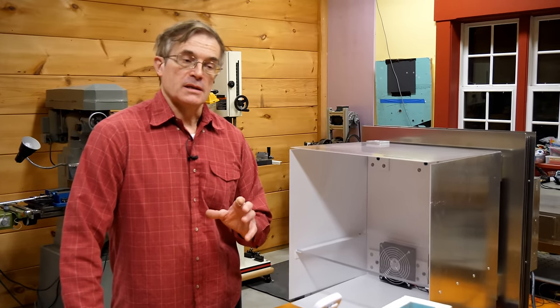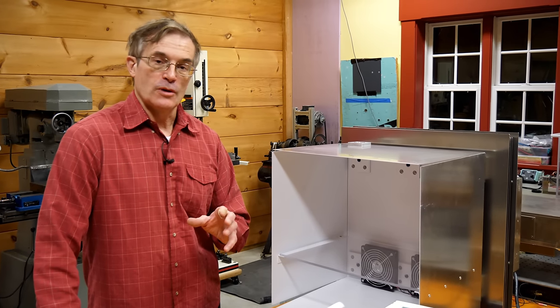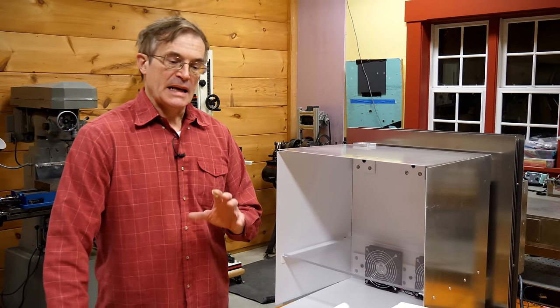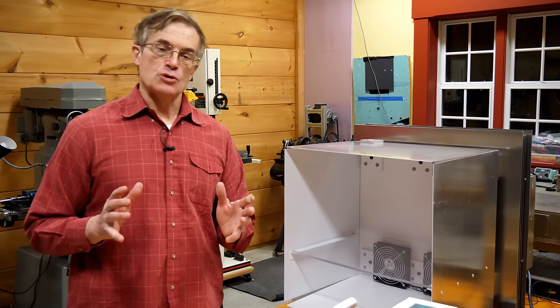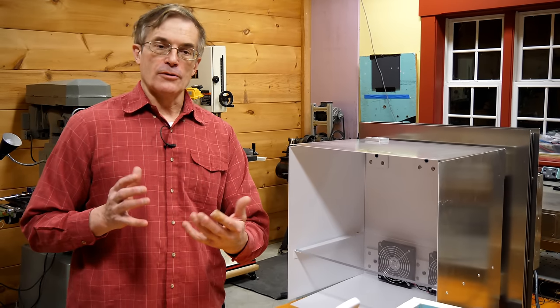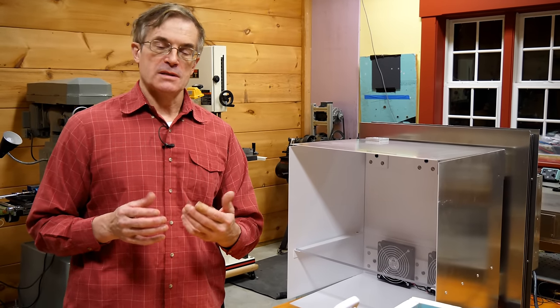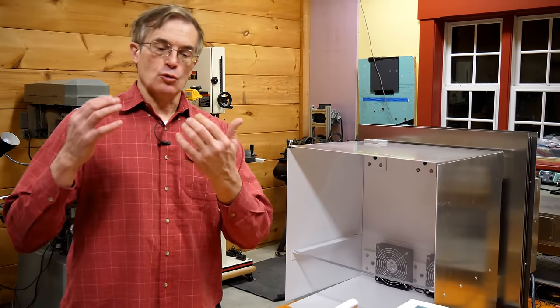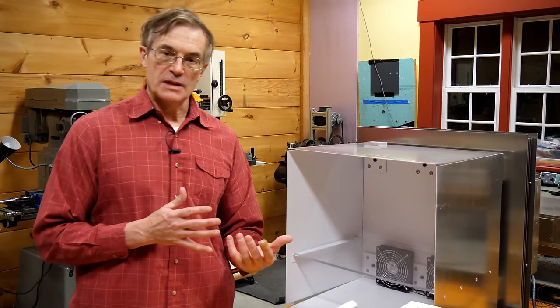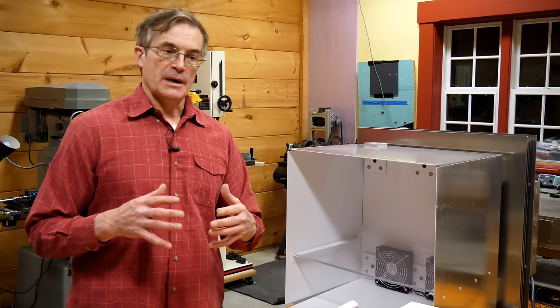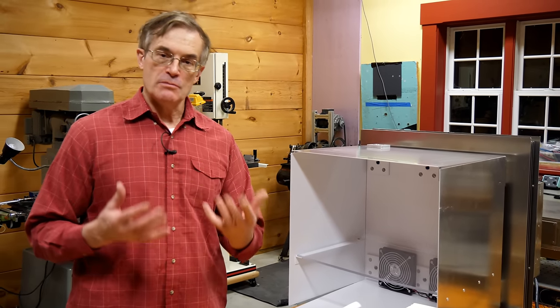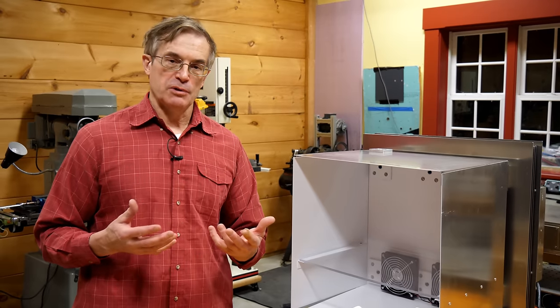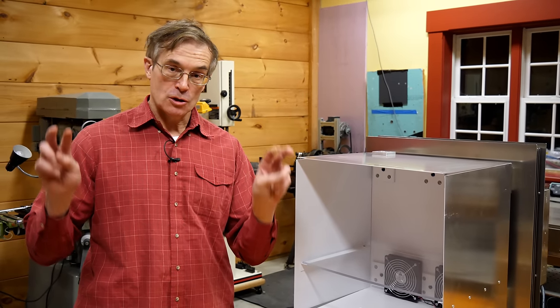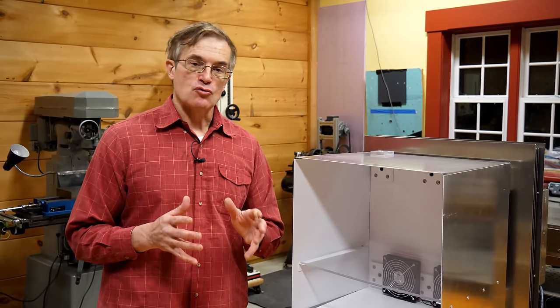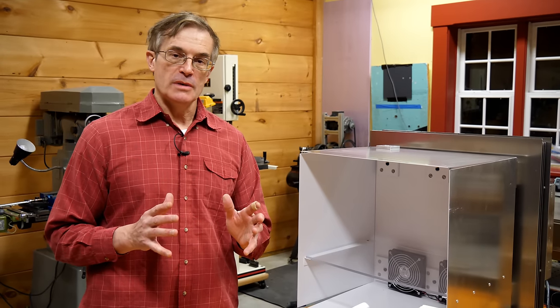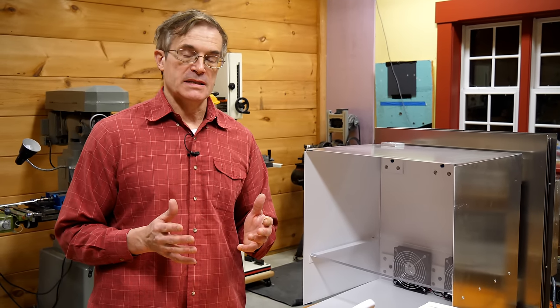If you've ever worked at a construction site, you're probably familiar with what's called a swamp cooler. In this kind of a device, a large low-speed fan will blow air through a mist of water droplets. The water will evaporate, will drop the temperature, and provide relief for the construction crew. But in the process, it adds a lot of humidity, and that can be kind of unpleasant, and that's why it's called a swamp cooler. Now, if you're in a very dry environment, that additional humidity may not be a bad thing. It may even be desirable.